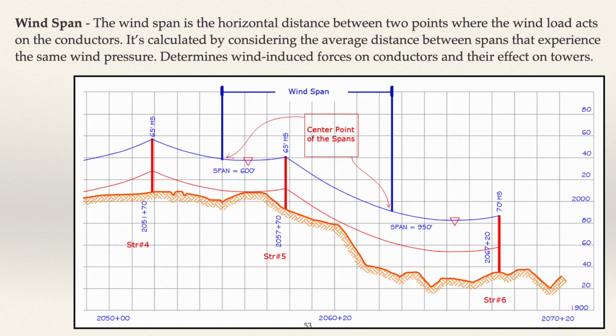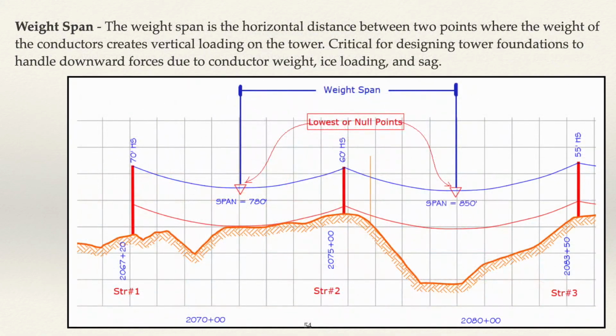Wind span. The wind span is the horizontal distance between 2 points where the wind load acts on the conductors. It's calculated by considering the average distance between spans that experience the same wind pressure. Determines wind-induced forces on conductors and their effect on towers. Weight span. The weight span is the horizontal distance between 2 points where the weight of the conductors creates vertical loading on the tower. Critical for designing tower foundations to handle downward forces due to conductor weight, ice loading, and sag.